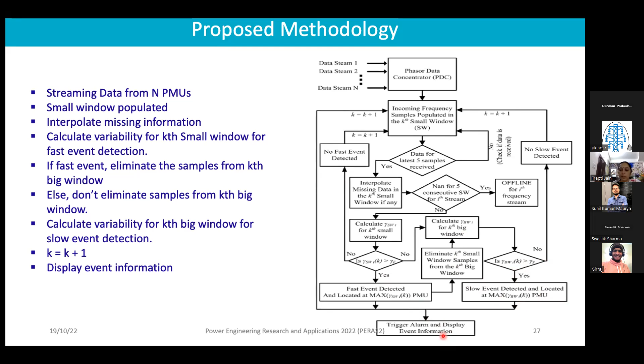Then we compare where the event is located. For all the PMUs, this variability will be compared. Whichever PMU has the maximum value of variability, the event will be located there. Because that window already contains data with the fast event, it will interfere with the slow event. So what we do is remove those samples from the kth big window, and the calculation is then done with 245 samples, not 250. We calculate the variability of the big window, and again check whether it is greater than the threshold. If not, no slow event is detected. If yes, then a slow event is detected, and it will be located at the PMU which has the maximum value of variability. Then the alarm can be triggered. So this is how the whole method works.